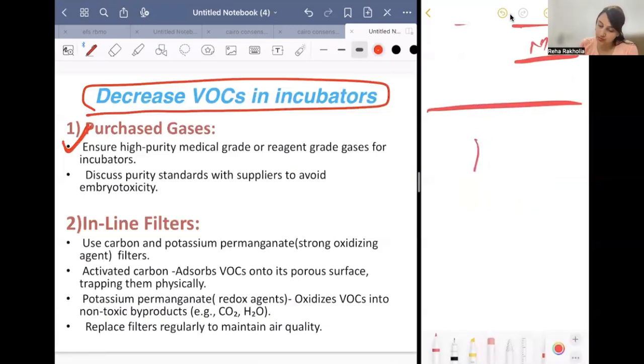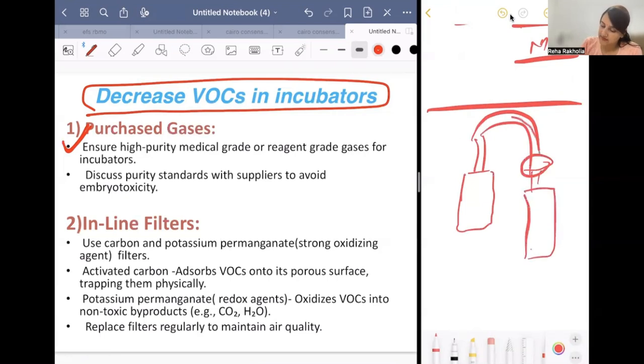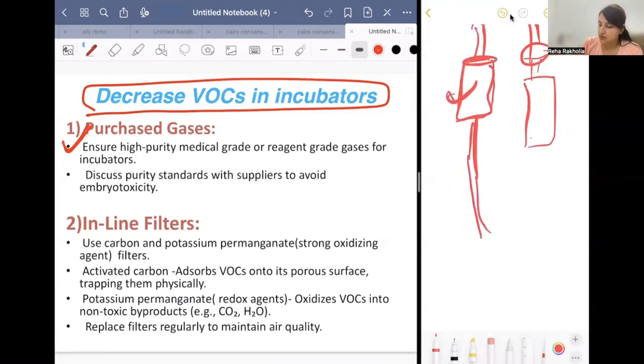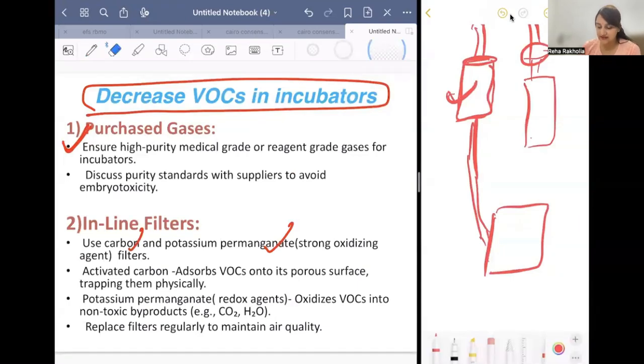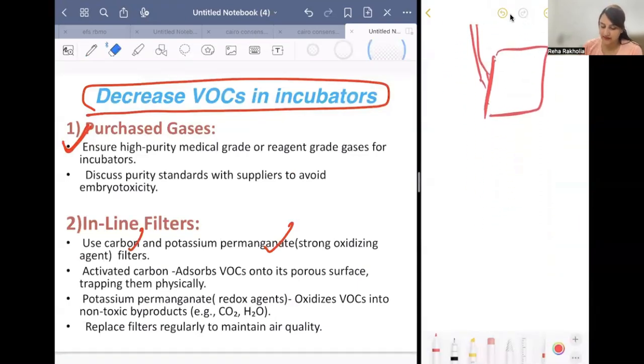The inline filter is on the gas line. See, the gas cylinder will be attached to this line, so there should be one filter here in the line. This is called the inline filter. Then through that filter, the gas should go to the incubator. This filter should use carbon and potassium permanganate. Potassium permanganate, as I already told you, is a strong oxidizing agent filter.